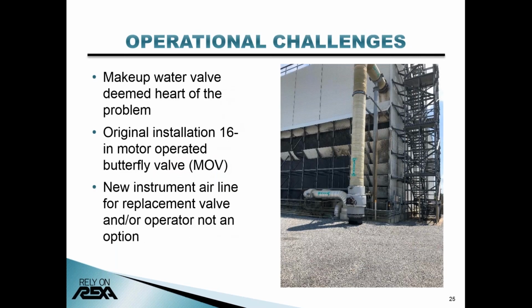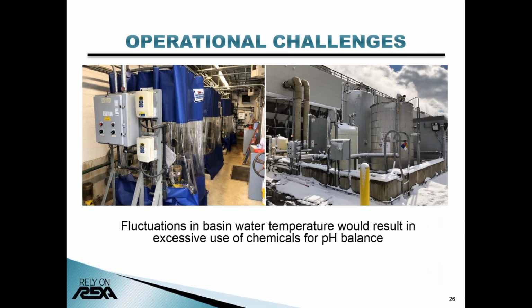The need for additional cooling water is what brings us to the problems at Longview Power. A 16-inch butterfly valve powered by a motor operator was originally installed in this makeup line. It was unable to accurately control the flow of this varying temperature water to the basin. The result was large slugs of very cold or very warm water that was added to the cooling circuit, causing water chemistry to vary widely and the excessive use of chemicals.